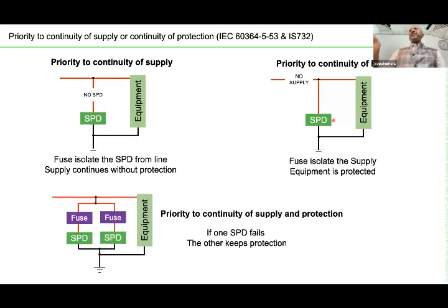Now, if you want priority to continuity of supply as well as protection, then you have to go for an SPD which sometimes has multiple varistors inside. So these SPDs are also there. We didn't bring the sample. I hope this is clear.